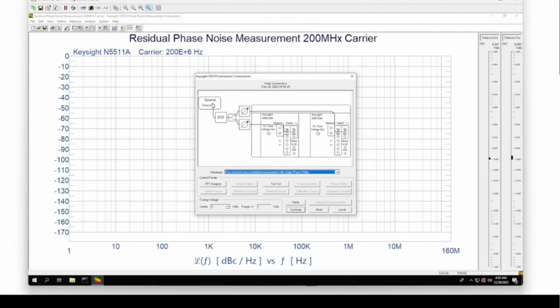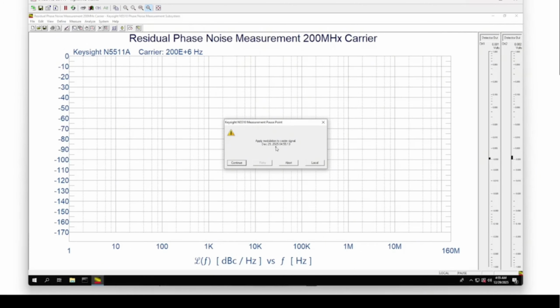So during my measurement, this is my setup. The stimulus will go through my DUT. In this case, because I am measuring the signal generator, this is just a cable. You want to be mindful of the length of that cable based on the carrier frequencies and the wavelength so that you don't go over it, or at least you have enough cable length to establish quadrature on both channel 1 and 2 detectors. Okay, so we're satisfied with this. Let's hit continue. So it asks me to apply modulation on carrier signal. This is when you will turn on PSG2. So let's go ahead and do that.